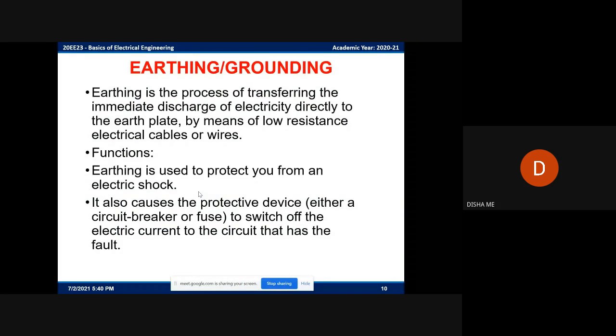Earthing or grounding. Earthing is the process of transferring the immediate discharge of electricity directly to the earth plate by means of low resistance electrical cables or wires. Functions. Earthing is used to protect you from an electric shock. It also causes a protective device, either a circuit breaker or fuse, to switch off the electric current to the circuit that has the fault.